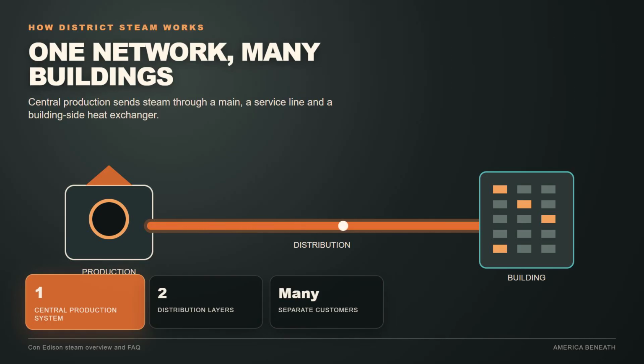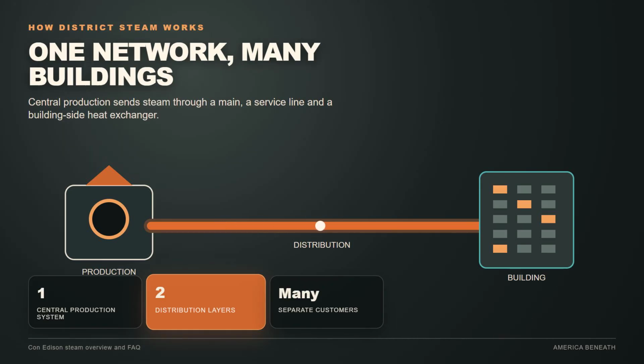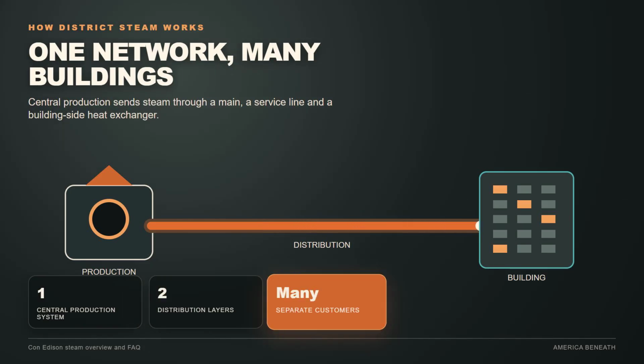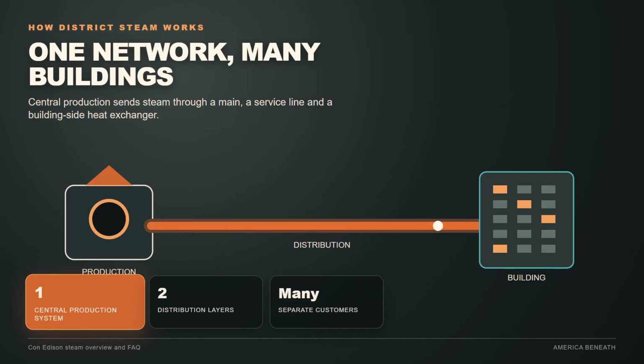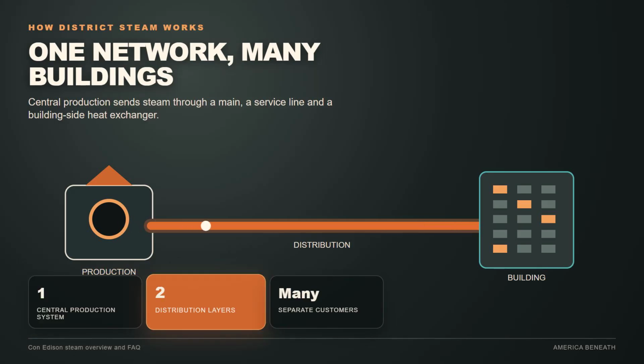Think of it as a shared thermal utility. Instead of every connected building producing all of its own thermal energy in a basement boiler plant, part of that production happens elsewhere. The customer buys the delivered steam and uses it through building-side equipment. The exact arrangement differs from one address to another, but the organizing idea stays the same: centralized production, a distribution network, and many separate customers. Once steam becomes a utility, one old boiler is no longer the right mental picture. The useful unit is a network. And networks survive for different reasons than individual machines do.